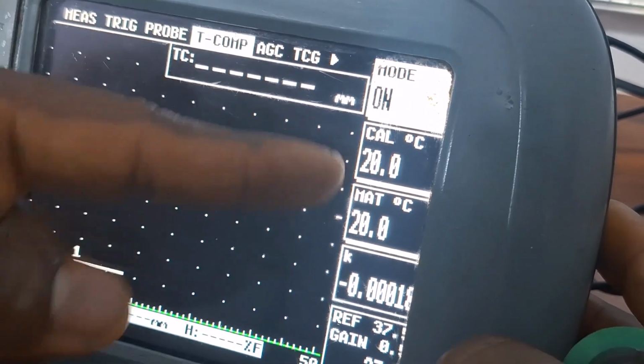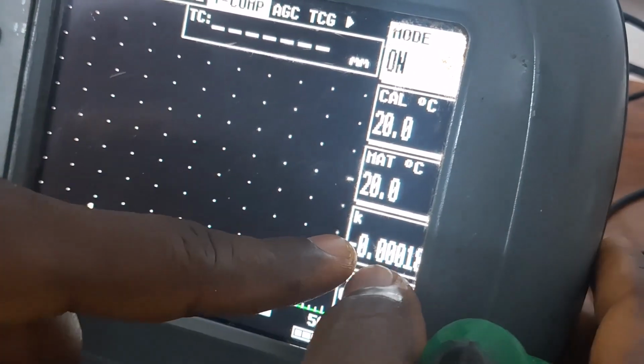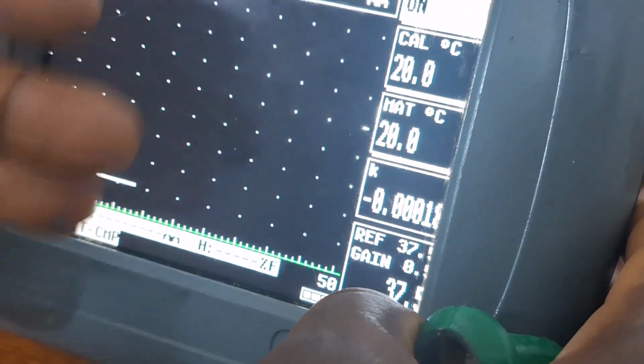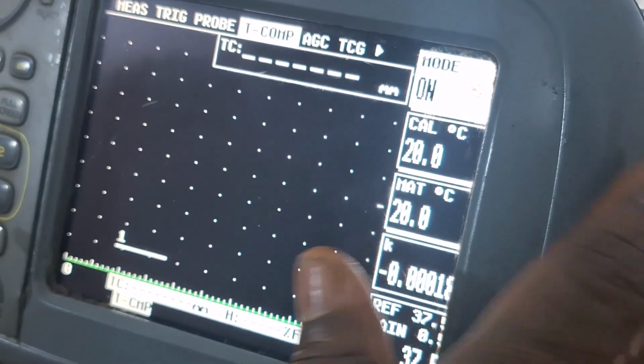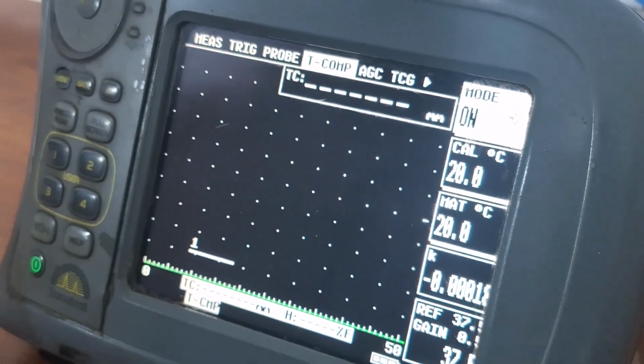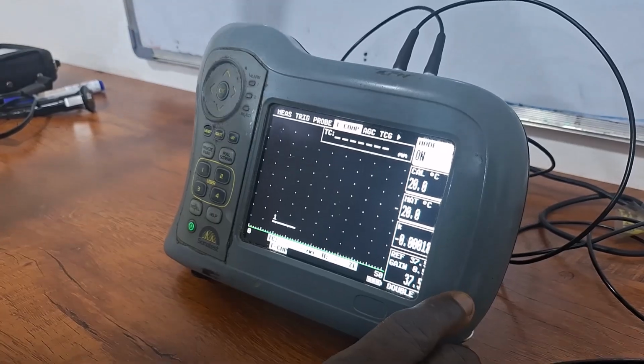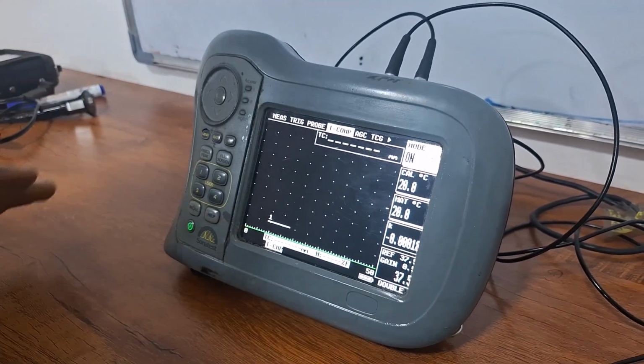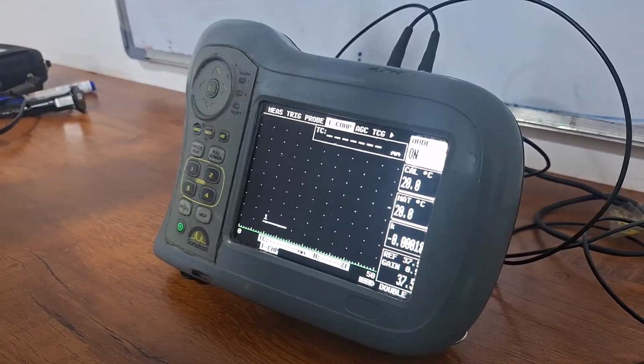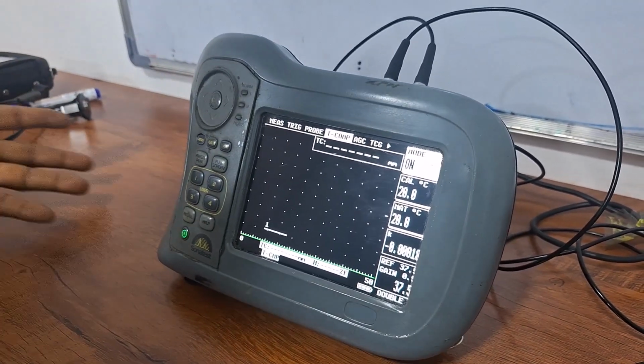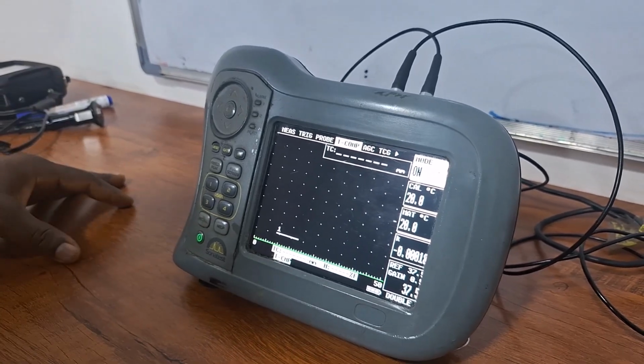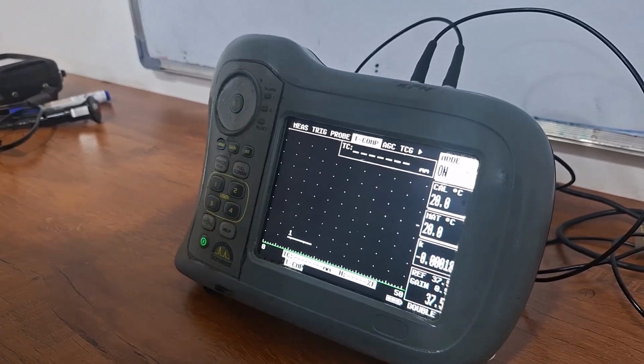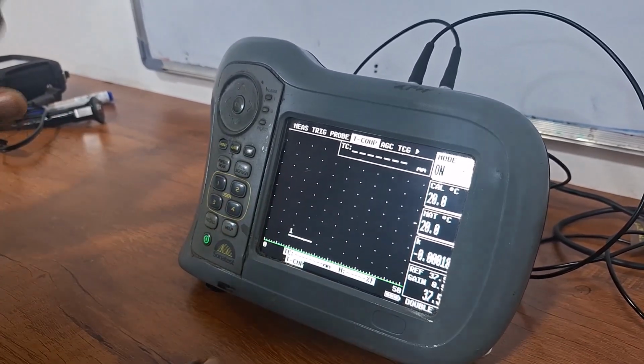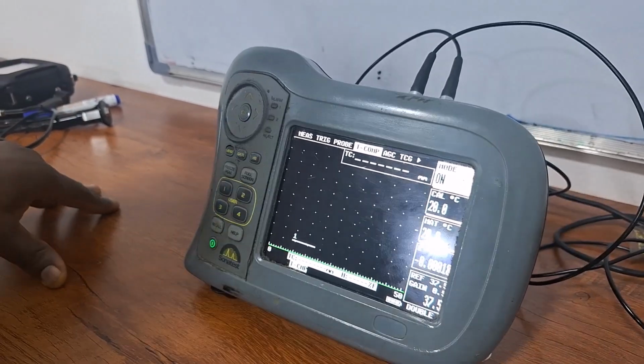Immediately you turn it on, you can now put your calibration temperature, your material temperature, and your temperature coefficient. Every material has its temperature coefficient, so always verify the temperature coefficient of the material, input it, and you are good to go. So what the unit does after putting these values, the equipment will automatically do the compensation for your temperature change, and if there are variations in thickness which is due to high temperature, the machine automatically calculates it and gives you the correct reading. It is very key that you do this. If not, you will be having readings that are out of your expected thickness.